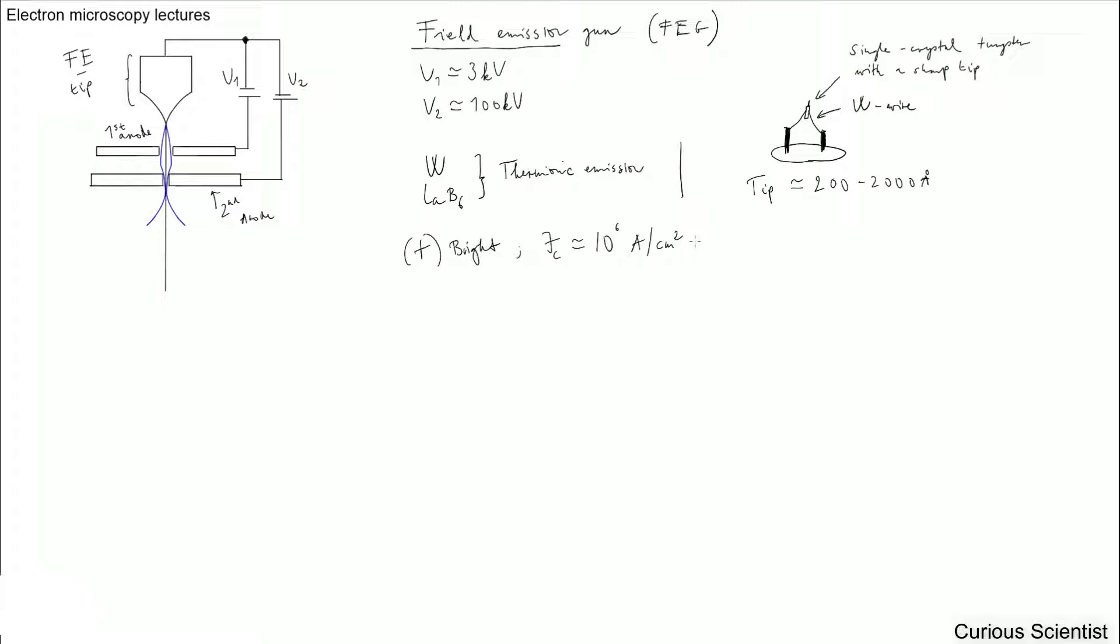And it's two orders of magnitude better than the lanthanum hexaboride tip. And the FEG can produce a focused spot smaller than 100 Å without any auxiliary lenses. So you don't need lenses and you already have very small spot size.